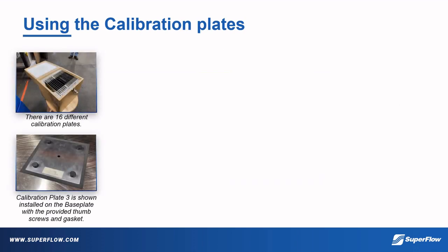There are 16 different calibration plates PowerTest keeps stored in a wooden box. These plates can be sold to customers, but are typically rented to customers or sent along with a technician to a customer location. Here below, calibration plate 3 is shown installed on the base plate with the provided thumb screws and gasket. Notice the markings toward the top of the plate. These are its identification numbers. When testing in intake mode, the plate must be installed with these numbers facing up.